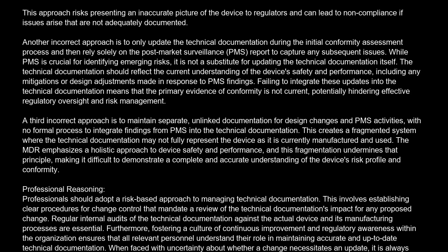The MDR emphasizes a holistic approach to device safety and performance, and this fragmentation undermines that principle, making it difficult to demonstrate a complete and accurate understanding of the device's risk profile and conformity. Professional reasoning. Professionals should adopt a risk-based approach to managing technical documentation. This involves establishing clear procedures for change control that mandate a review of the technical documentation's impact for any proposed change. Regular internal audits of the technical documentation against the actual device and its manufacturing processes are essential.